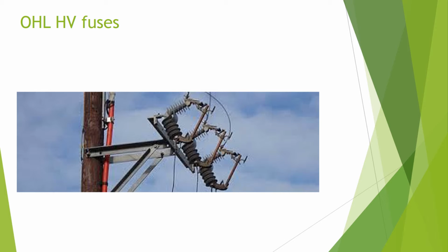The fuses are installed with the same insulated operating rods used to operate ABSDs. Overhead line fuses are usually used to protect large transformers and overhead line radial spurs. They are mounted to the pole under the overhead line and are connected by underslung jumpers.